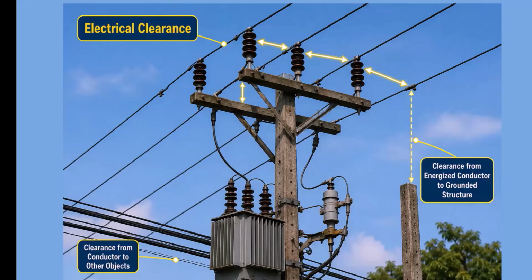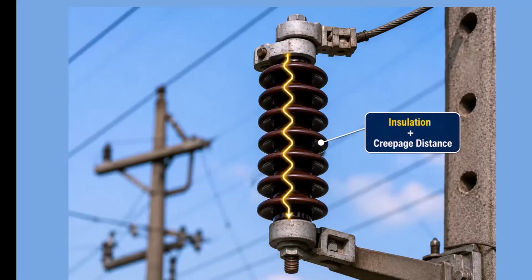So now when you see spacing, you should think about electrical clearance. These conductors cannot simply be placed wherever we want. Their spacing has to help prevent an electrical arc from jumping between phases or from an energized conductor to ground. Now look at these ribbed components. These are the insulators. Their job is not only to mechanically support the energized conductors, they also electrically separate those conductors from the grounded pole or structure.